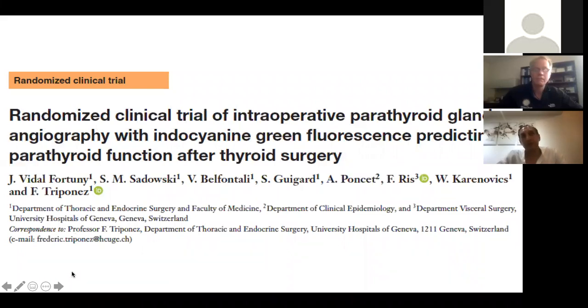Regarding OR lights: with ICG and the SPY-PHI, we don't need to turn the room lights off, but we do need to move the spotlights away from the field — too much direct light creates too much background. With the FluoBeam for autofluorescence, you need to turn the room lights off entirely since autofluorescence is more subtle. Fernando confirms the same: for autofluorescence, room lights off; for ICG, just move the OR lights.